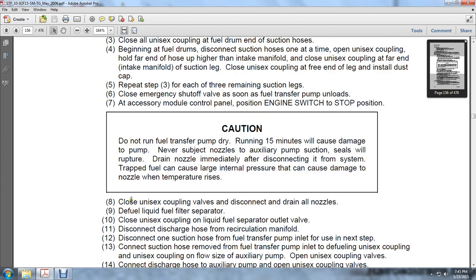Okay, continuing. Close unisex coupling valves. Disconnect all the drains of all the nozzles. Defuel the liquid fuel filter separator. Close the unisex coupling on the liquid fuel separator outlet. Disconnect the discharge hoses from the recirculation manifold. Disconnect the suction hose from the fuel transfer pump inlet for use in the next step.